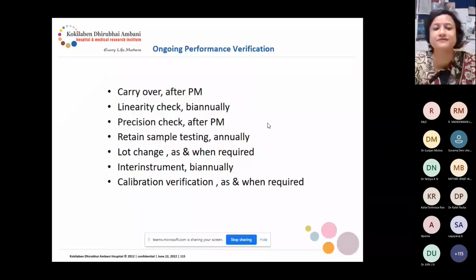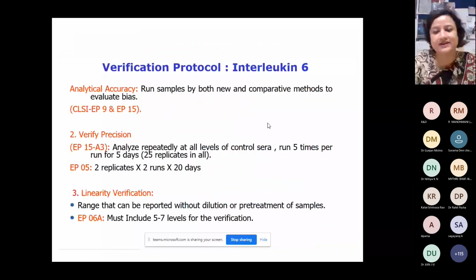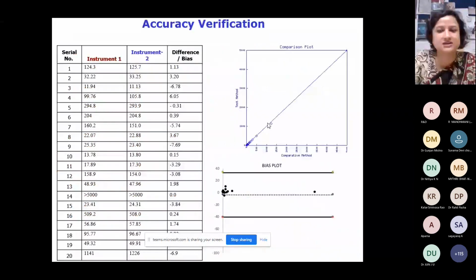verification, very important. Inter-instrument, lot-to-lot verification, many people do it very incorrectly. So maybe some days I will show how to calculate the critical difference in lot-to-lot verification. So I got non-compliance, and from that we actually evolved. And inter-instrument verification is biannually, calibration verification as and when required. And this is the verification protocol.